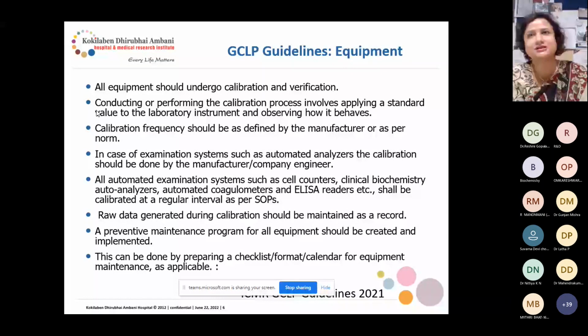Though I saw, when we were checking the calibration records, that we have all the calibration certificates, and for many of the instruments, the IVD manufacturers give one documentation. Nowadays many IVD manufacturers don't give a calibration certificate. They give documentation that calibration has been done during the preventive maintenance, and as per the norms, they give one letter.